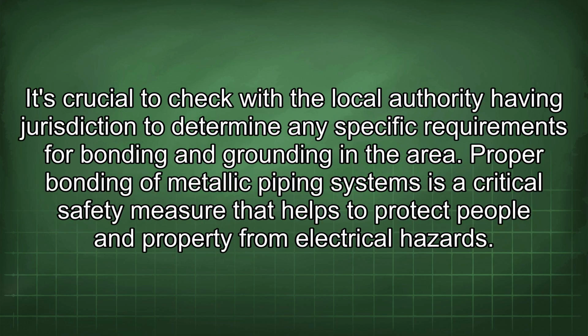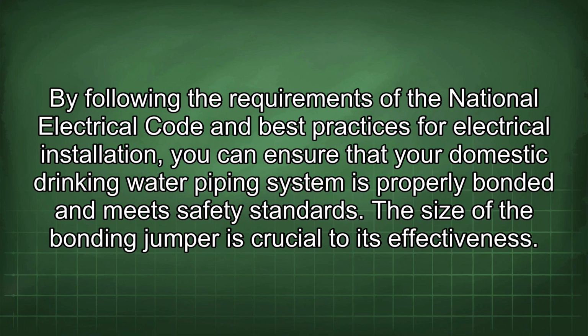It's crucial to check with the local authority having jurisdiction to determine any specific requirements for bonding and grounding in the area. Proper bonding of metallic piping systems is a critical safety measure that helps to protect people and property from electrical hazards. By following the requirements of the National Electrical Code and best practices for electrical installation, you can ensure that your domestic drinking water piping system is properly bonded and meets safety standards.